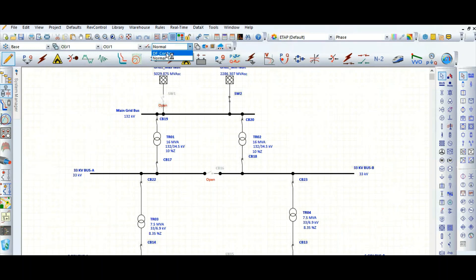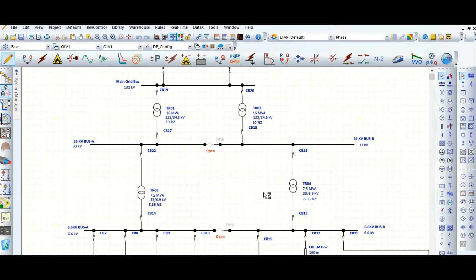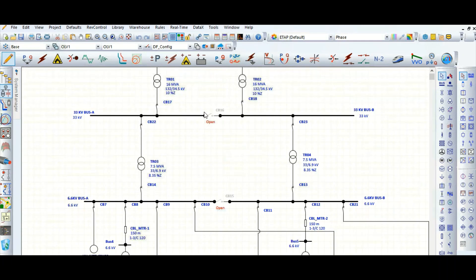Now we need to define the switch or circuit breaker status. The bus coupler breaker will be open, and the two incomer circuit breakers will be closed. Just toggle the breakers with the help of the 'T' key on the keyboard. Now this is the dual feeder configuration.